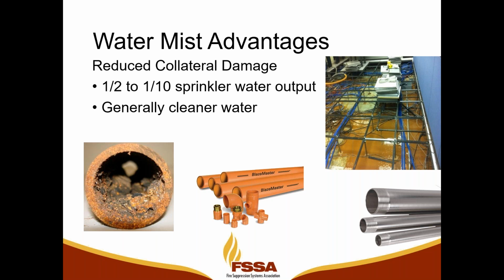microbiologically influenced corrosion. So when we have a water mist system, we're typically using potable water. That is, most water mist systems require that you use water that's drinkable. And then that water is going to be flowing through a stainless steel pipe in all likelihood. Sometimes we use copper, and then where we can regulate the pressure down to below 175 psi in a wet pipe system, we can even use CPVC pipe on a water mist system.